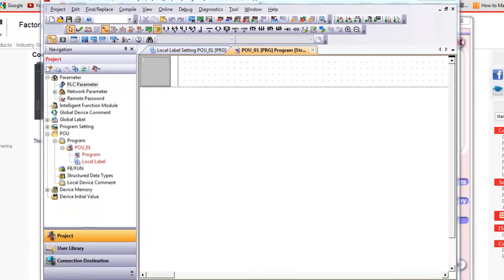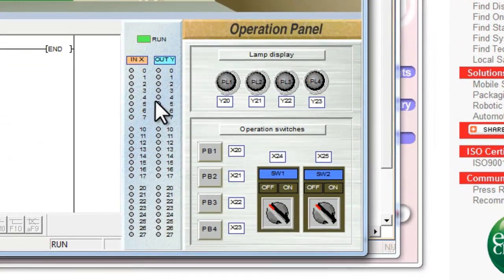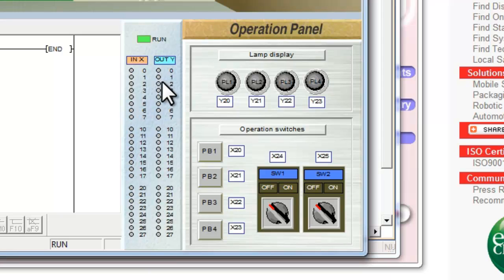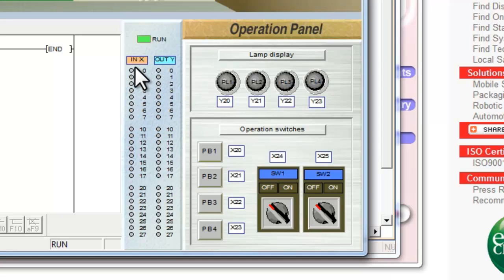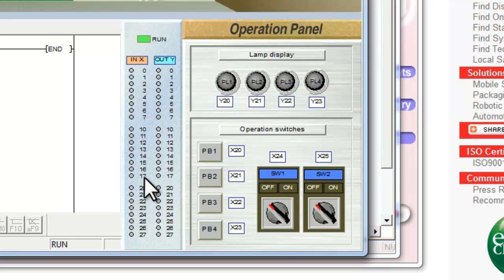For FX series, the IO is organized a little bit differently. Here you can see in a simulation of an FX PLC, you can see this is an FX48MR. In other words, you have 24 inputs and 24 outputs. These are organized in blocks of 8 inputs and 8 outputs. In an FX system, IO is organized in an octal format. So you have X0 through X7. X8 and 9 are not used. So the next input then becomes X10, X11, X17. And then again it jumps to X20. This is very important to note in an FX system.